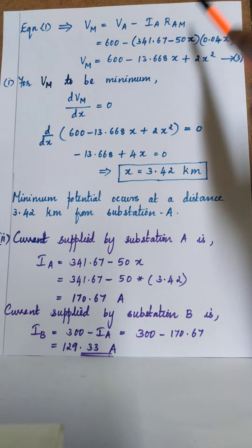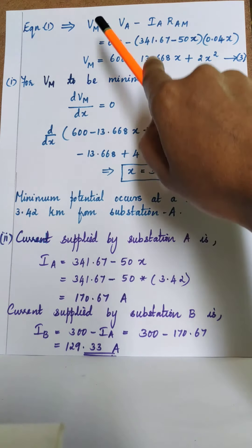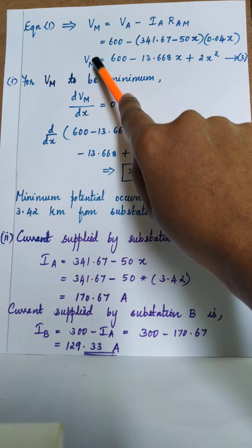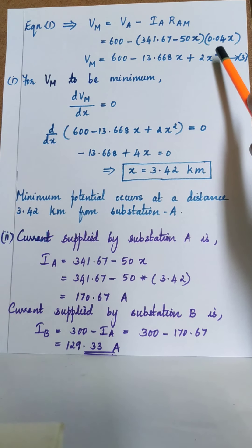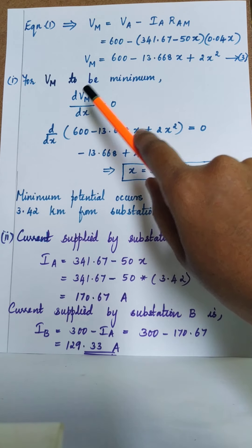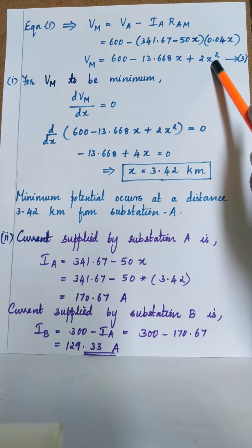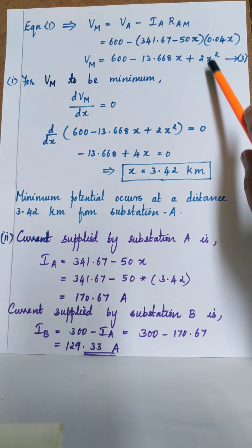From equation one, Vm = Va minus Ia times Ram. Our aim is to find the distance x for which Vm will be minimum. Substituting for Va, Ia, and Ram, we get Vm in terms of x: Vm = 2x² minus 13.668x plus 600. For Vm to be minimum, the differential of Vm with respect to x should be equated to zero.